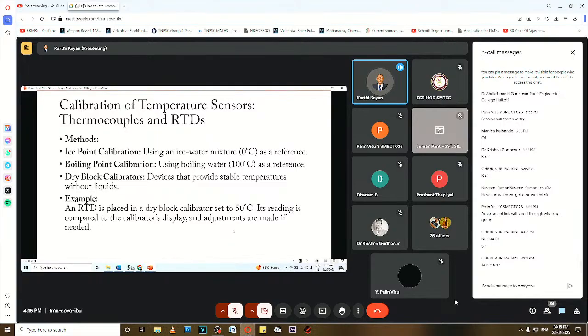Next, calibration of temperature sensors. What is the calibration of temperature sensors? Temperature sensors include thermocouples and RTDs. What methods are used? Ice point calibration uses an ice water mixture at 0 degrees Celsius as a reference.